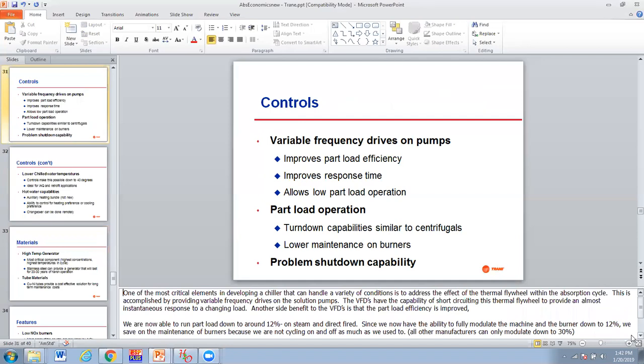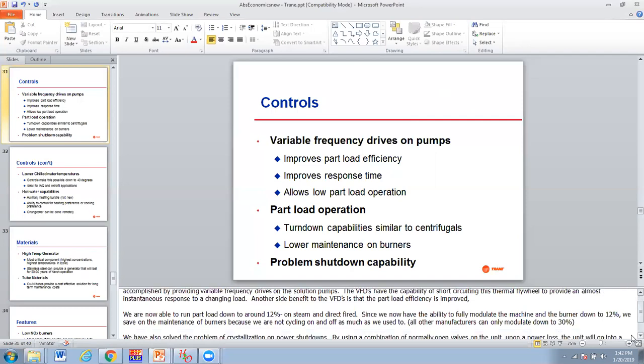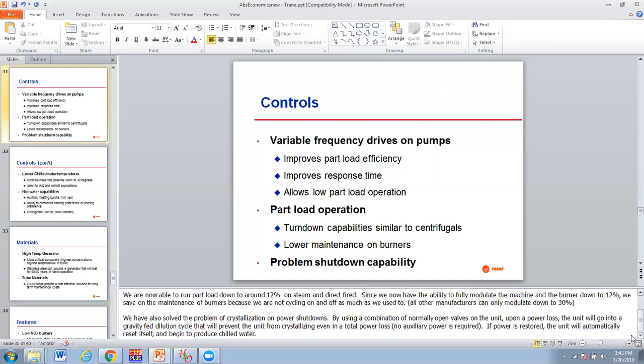One of the most critical elements in developing a chiller that can handle a variety of conditions is to address the thermal flywheel effect within the absorption cycle. This is accomplished by providing VFDs on solution pumps. VFDs have the capability of short-circuiting this thermal flywheel to provide an almost instantaneous response to changing load. Another side benefit of VFDs is that they improve part load efficiency. We're now able to run part load down to about 12%. So it has an 8-to-1 turndown, which is really impressive and significant on steam and direct fired.